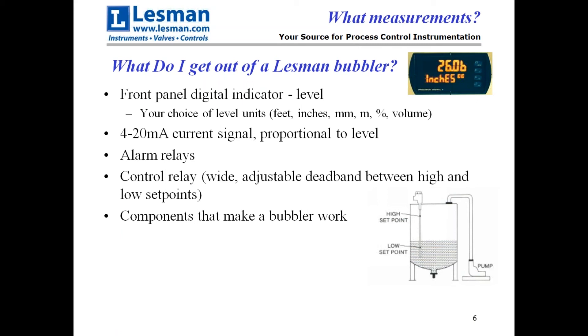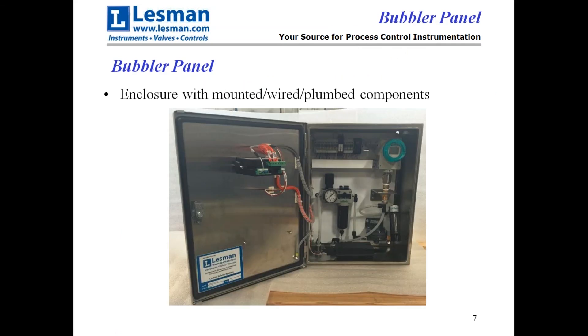Here's an example of a bubbler panel. You can see the digital indicator on the back side of the door. There's a pressure transmitter, a constant flow regulator with a rotameter, and a coalescing filter with its pressure gauge. The little black box on the bottom is a heater with a thermostat, and there are electrical wiring terminals up on the top. That's the spread of a control panel.